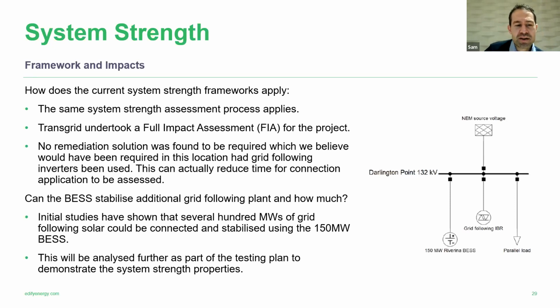The next part of the question is whether the BESS can actually stabilize additional grid following plant, and by how much. We set up specific studies connecting a grid following solar plant in parallel to the BESS to see the impact. We modeled it without the grid forming inverter first and tuned it to ensure there were stability issues, then brought on the grid forming BESS. The results were very positive: the 150 megawatt BESS could stabilize on the order of greater than 500 megawatts worth of solar at this location, showing a significant ability to provide system strength remediation for other plants.